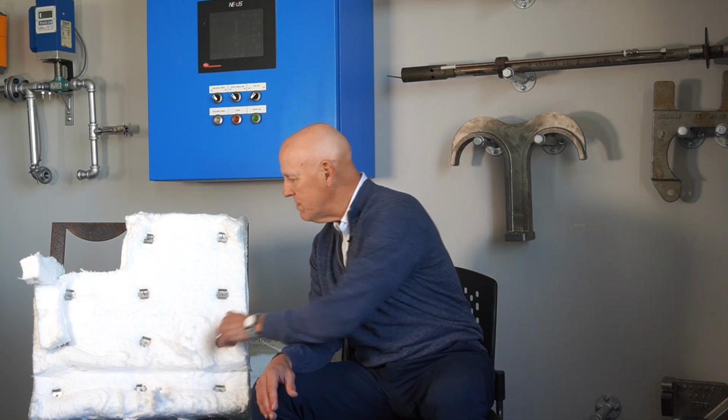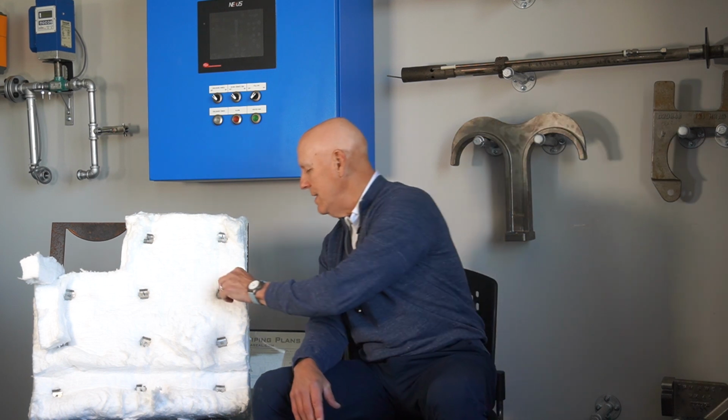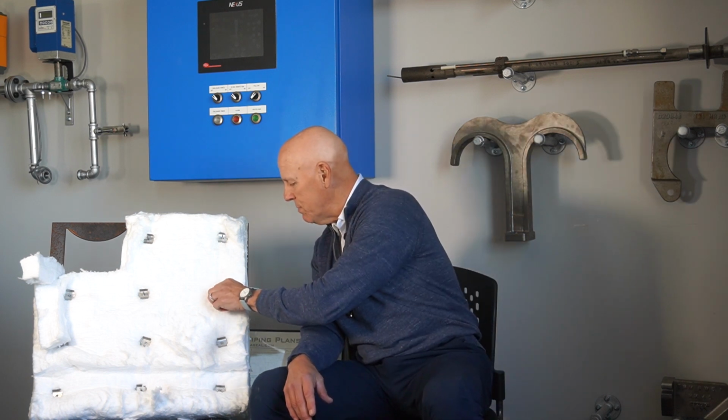Now, I said earlier that typically you're 1600 degrees on the surface, so typically these are fine. Sometimes flames get a little bit long. If they get long and they hit a wall that has these guys and the gas temperatures are 2000, these anchors, actually the keepers themselves, will fail, pop off, and you can have some refractory loss.